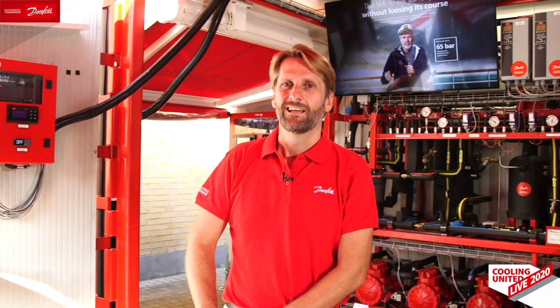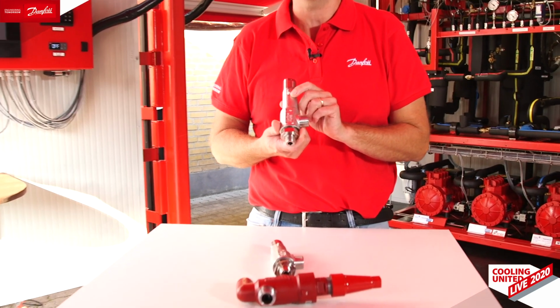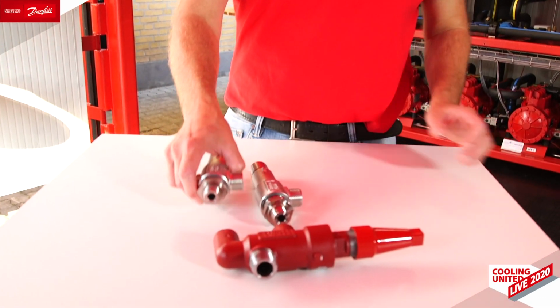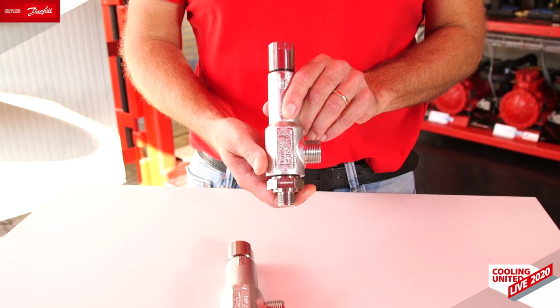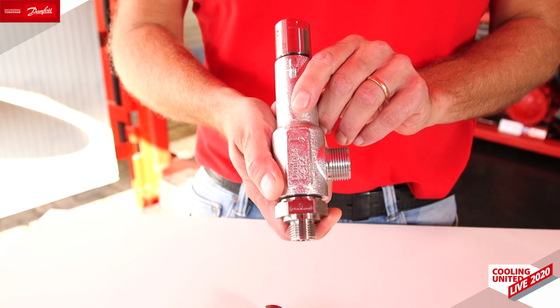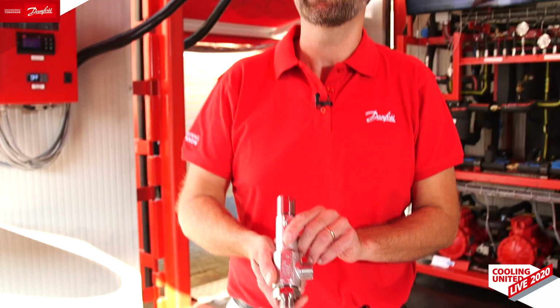Thank you, Anja. Hello, and I would like today to present the 2 new products at Danfoss: safety valve SFA10, coming together with a DSV changeover valve, products which are designed according to industrial standards. It's applicable for medium and low charge industrial systems, but also CO2 transcritical small to medium sized systems. With the industrial design that we are introducing here, we are addressing some of the most common issues in CO2 transcritical systems with leaks, with sudden reliefs and lost charges, something that annoys everyone in the industry, I think.